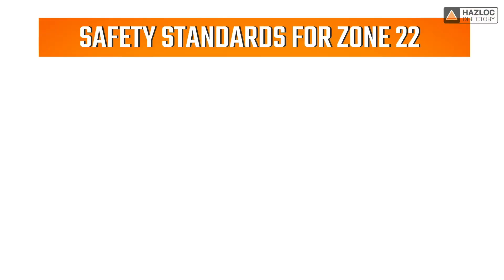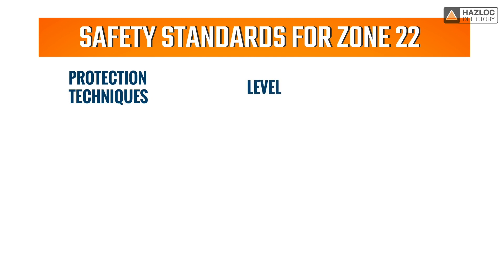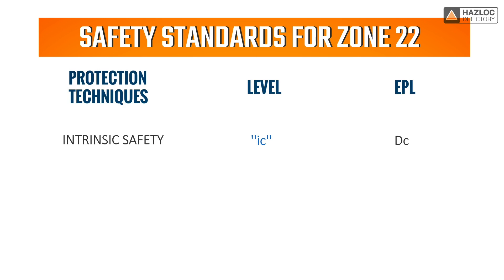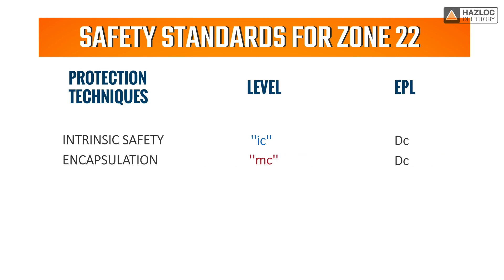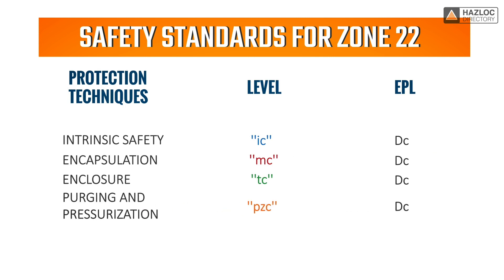In order to be certified as compliant with safety standards for Zone 22, an electrical device must be protected by one or more of the following protection techniques: intrinsic safety with level of protection IC, encapsulation with MC protection, protection by enclosure with TC protection, and purging and pressurization with PZC.